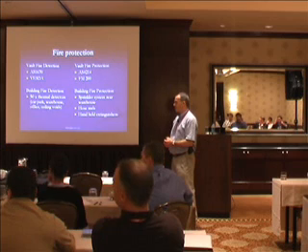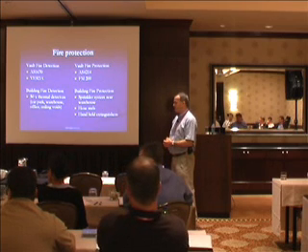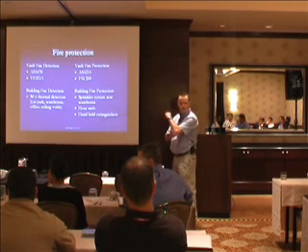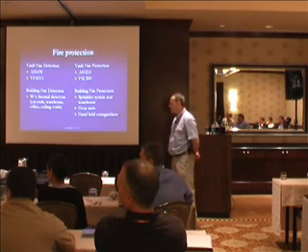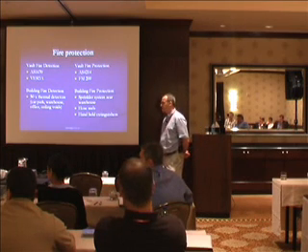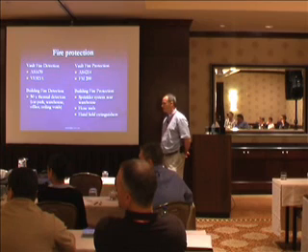What kind of lighting do you recommend? What does everybody use here? What's the ideal lighting? T8, fluorescent? Let me tell you, my fluorescent light ballast went off and it cost me $32,000 for the new FM200 discharge. So we put all new ballasts in, and I was told not to put in incandescents.